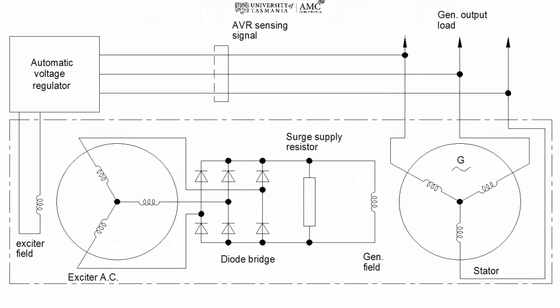So we're looking at a schematic view of our AVR, or automatic voltage regulator. Basically, here is the AVR, and this is our alternator, which comprises our exciter on this end and our generator on this end. In the middle is the rotor, and on both ends is our stator, one for the exciter, one for the generator.